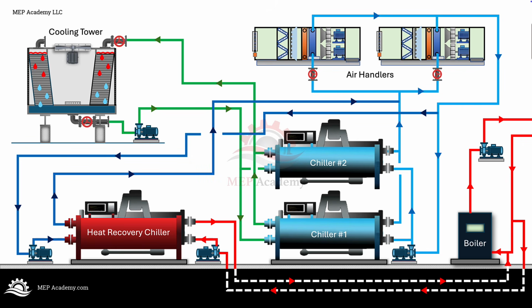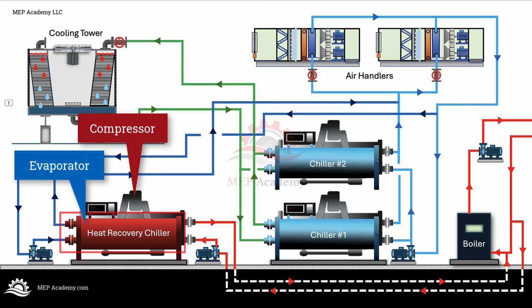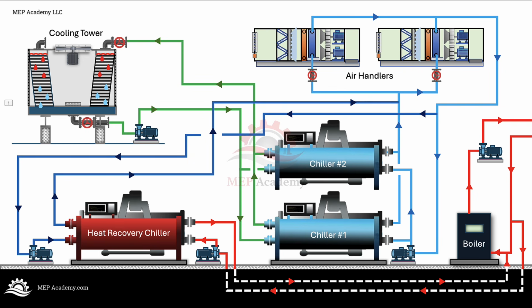The chilled water absorbs heat from that load and returns warmer to the chiller. Inside the evaporator, the refrigerant absorbs the heat from the chilled water. The compressor raises the pressure and temperature of the refrigerant. Then the condenser transfers that heat into a hot water loop. That heating load could be reheat coils, perimeter heating, domestic water preheat, makeup air heating, or another system that needs heat. The hot water gives up heat to the load and returns cooler to the heat recovery chiller. The cycle continues. The chilled water side removes heat from one part of the building. The hot water side delivers that heat to another part of the building.